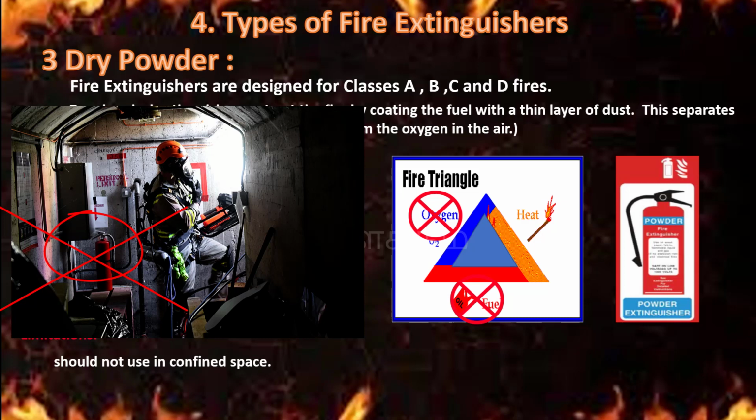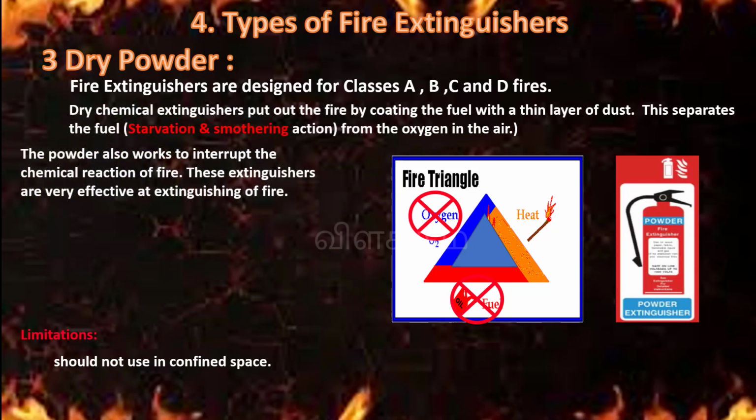These extinguishers are very effective at extinguishing fire. The limitation is that they should not be used in a confined space. This is very important, because in a confined space the powder causes oxygen deficiency. Next one.